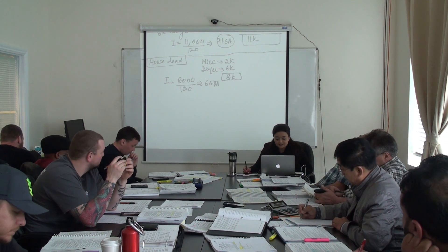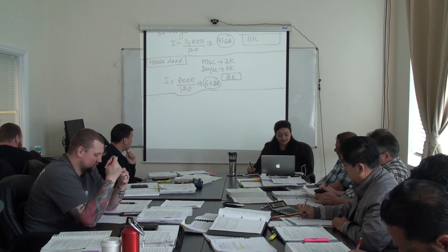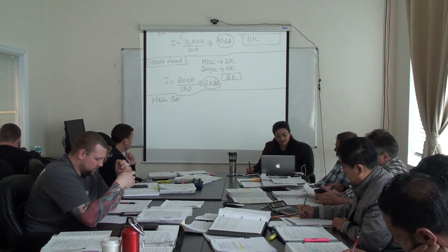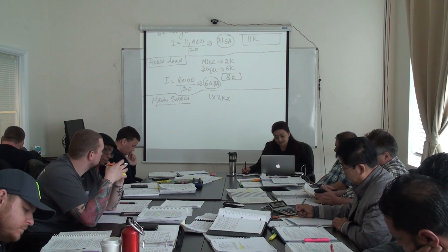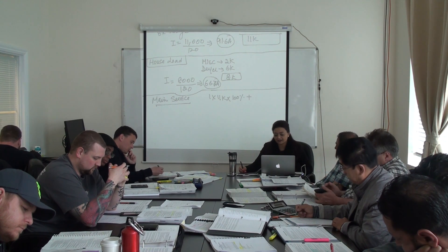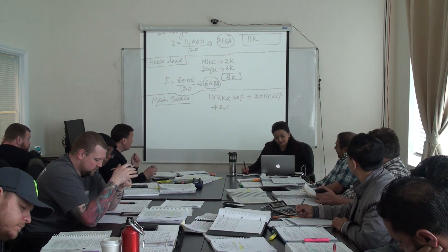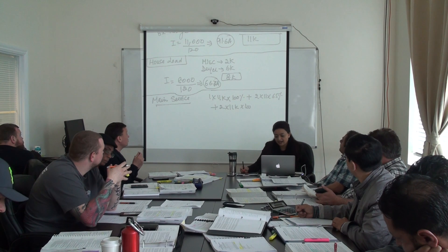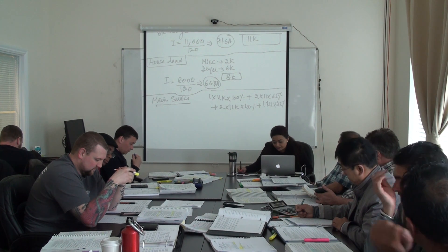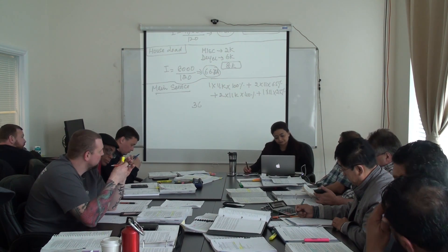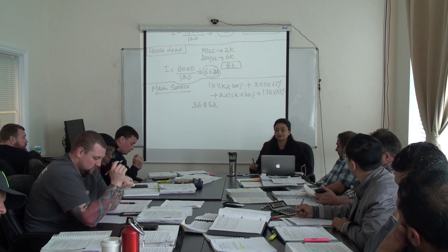All right, last thing left is main service calculation. In main service, Derek, how many suites are given? Six. So first suite is 11K at 100%. Because there is no heat, we are not kicking anything out. The next two guys are at 65%, the next two are at 40%, and the last guy will be at 25%. 1 times 11 plus those calculations — we get 36.85K. Guys, make sure you check the math — that's where we had trouble last time.